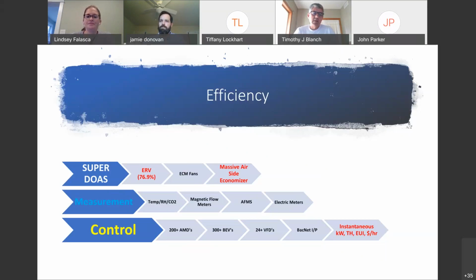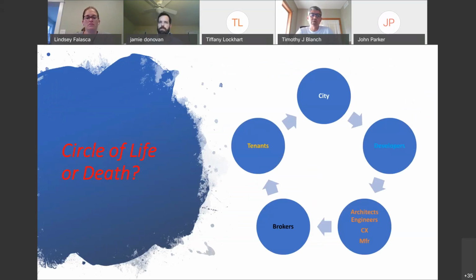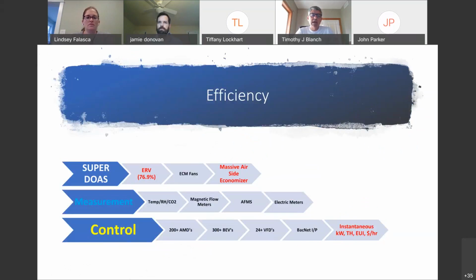So if you think of a riser diagram, we're putting all the primary air out through the zones in these AMDs per floor, and then we're doing the same thing with the restrooms and the return from the tenant spaces on every floor. So you essentially are balancing your building constantly. It's like you have 10 balancers on board. All right, so that is something very critical that I won't spend any more time talking about, but it's absolutely critical to the efficiency and how well the building works.